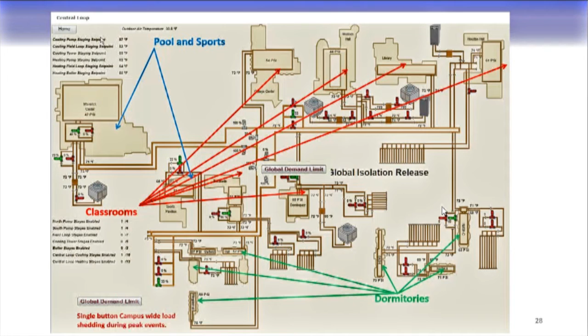So, single button campus-wide load control, load shedding at peak events. Second, reduce cooling tower water, reduce electric load. Originally, 3,400 tons was one of the original design conditions. It calculated water use of 14.5 million gallons a year, and the load to run the cooling tower transfer pumps and fans and everything else is about 784 kilowatts, almost a megawatt. With this district system, the existing system, I have a couple of old towers that we picked up along the way. I've got a total of 750 tons. We use 4.5 million gallons a year, a 10 million gallon a year reduction at the site.